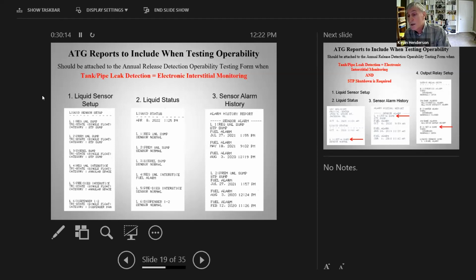And of course, if they have alarms after you leave, then that will go away. But you have that part of the permanent record of your test. You printed that history report when you were there before you left, and it became a part of your test report. That's how you prove that you actually made it go into alarm.